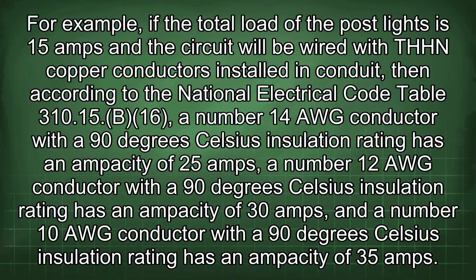For example, if the total load of the post lights is 15 amps and the circuit will be wired with THHN copper conductors installed in conduit, then according to the National Electrical Code Table 310.15(B)(16), the number 14 AWG conductor with a 90 degrees Celsius insulation rating has an ampacity of 25 amps.